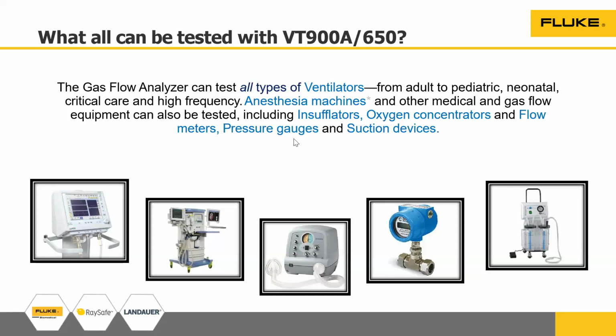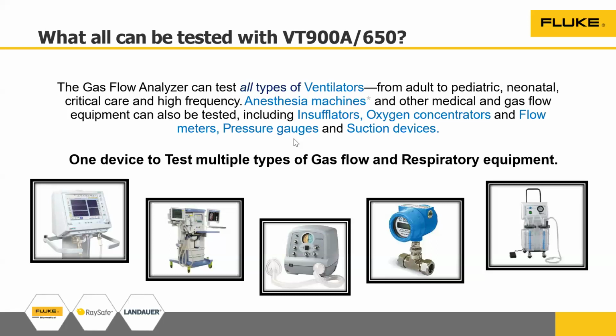When there are periodic checks, because if there is an oxygen leakage from, suppose, one of the oxygen flow meters, pressure regulators or pressure gauges inside the central pipe gas lines, the oxygen pipelines inside the hospital or ICU, and it goes undetected, then definitely if there is any small spark, that will add to a fire. That is why regular testing can prevent this kind of extreme and unfortunate incident. Basically, one test device can help you test so many devices: ventilators, anesthesia machines, flow meters, insufflators, and so many other devices, including a basic thing like a suction machine.